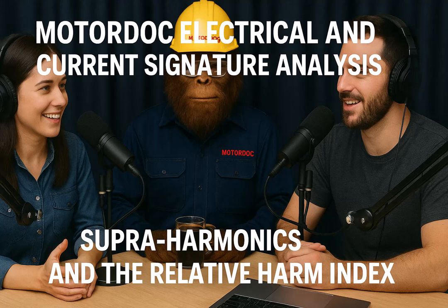Now, one source introduces this thing called the Relative Harm Index, RHI. What's that about? How does it help quantify the danger here? Right, the RHI. It's a metric developed to better assess the potential damage from harmonics, especially these supraharmonics. It tries to quantify the relative harm compared to the fundamental frequency, like 50 or 60 hertz. Think of it like a danger score for high-frequency electrical noise. Helps you prioritize. A danger score. How is it calculated? What's the idea behind it? It considers two main things: the amplitude, the dB level of the harmonic relative to the fundamental current.